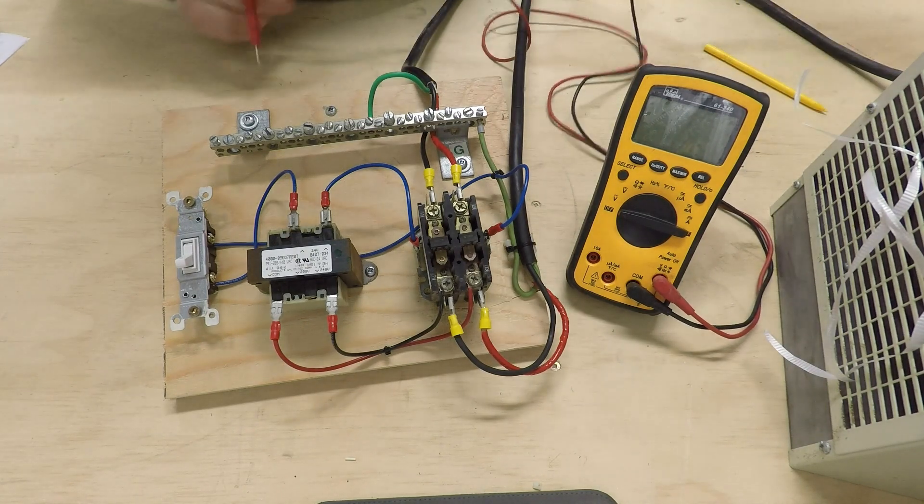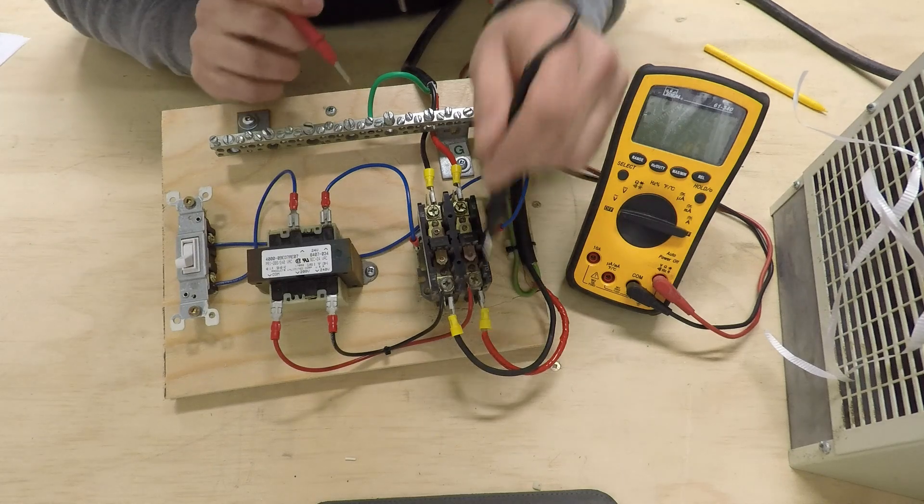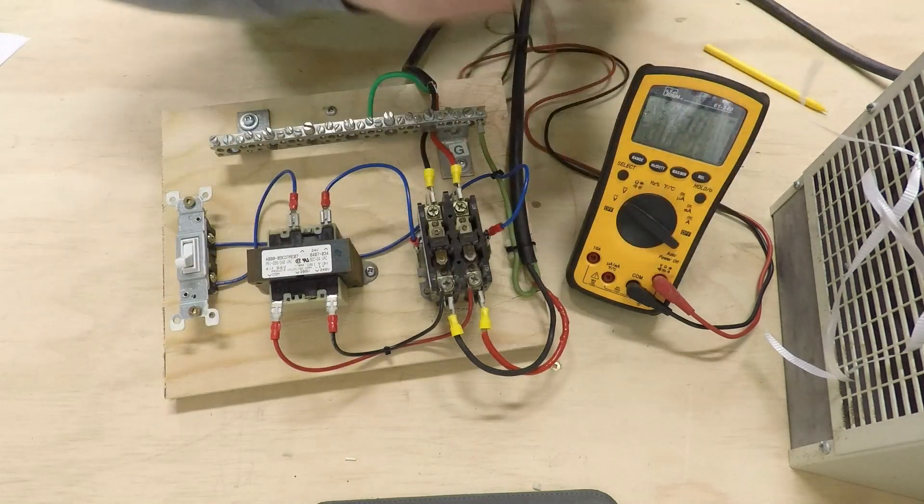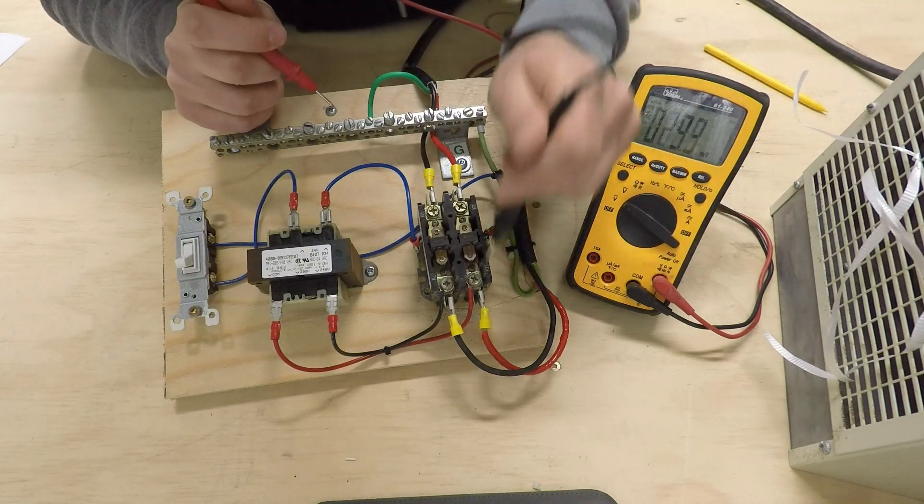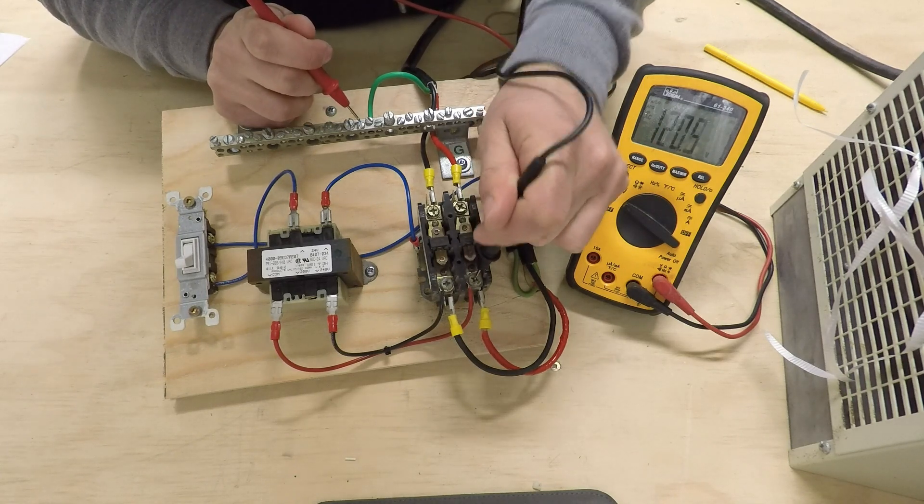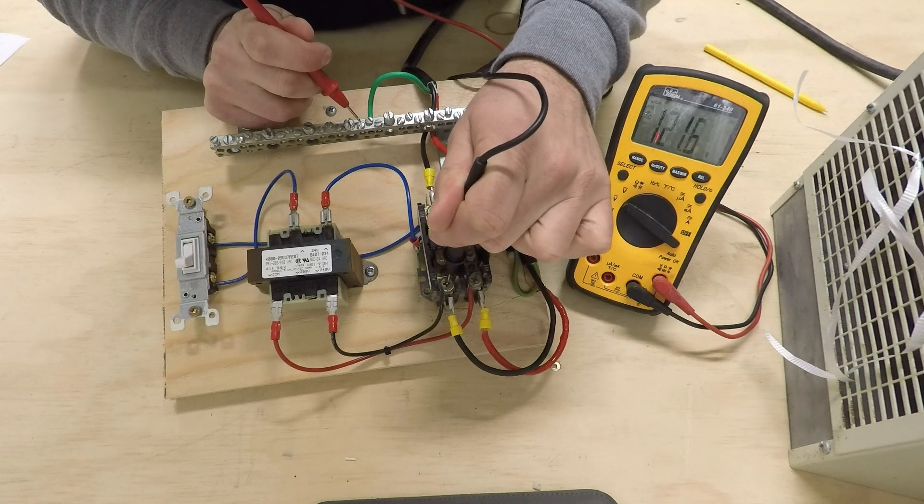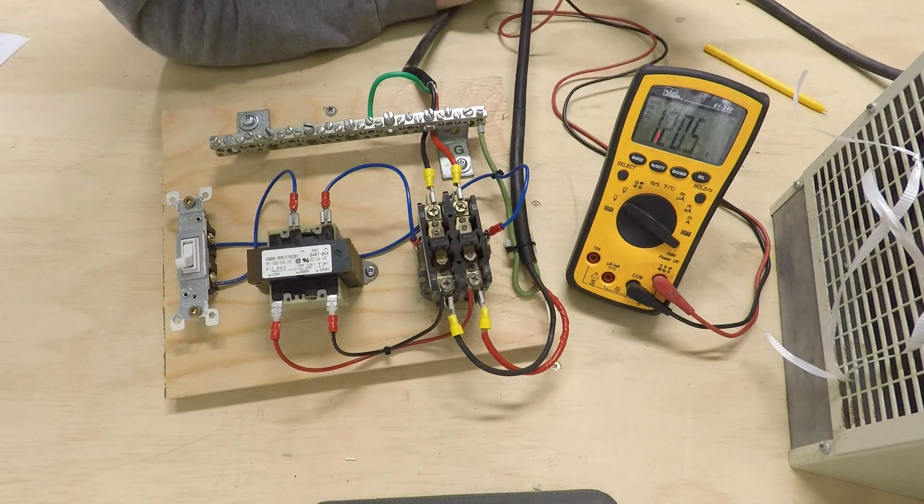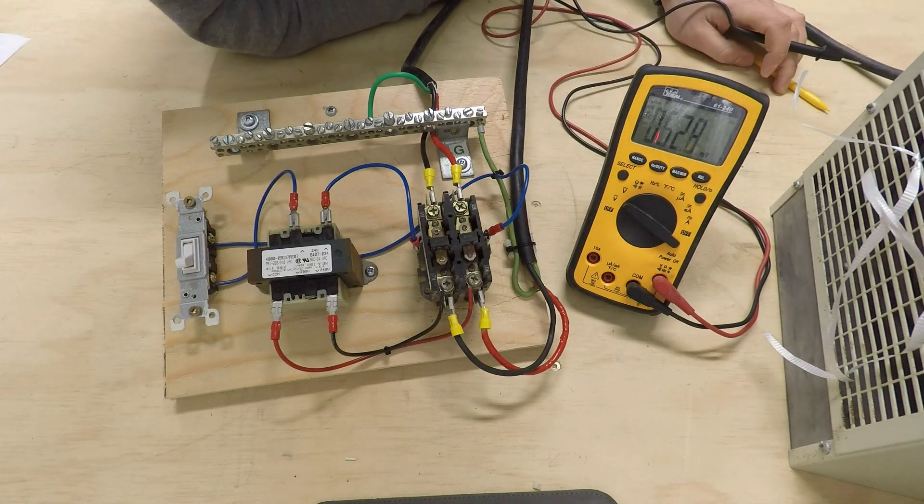Okay, the breaker's on right now, so we're going to have 120 volts on each phase coming into the line side of the contactor. So we'll just check that. Yeah, approximately 120 and approximately 120. So 120 plus 120 gives you your 240 volt supply.